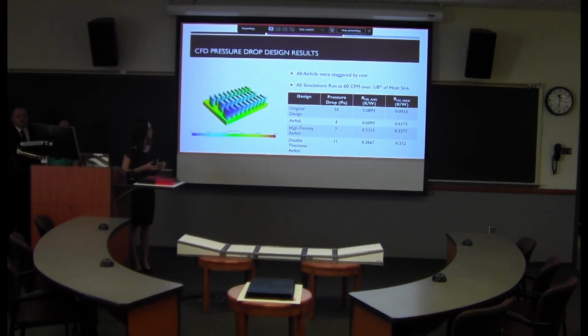And so even though we didn't quite match the resistance of the original design, as you can see there, you can also see that we didn't even come close to matching the pressure drop of the original design, which is a very good thing.